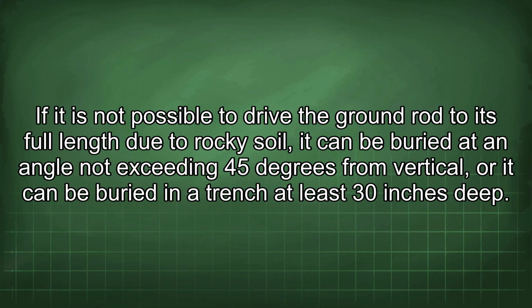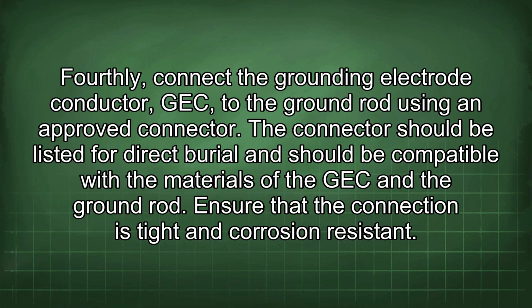If it is not possible to drive the ground rod to its full length due to rocky soil, it can be buried at an angle not exceeding 45 degrees from vertical, or it can be buried in a trench at least 30 inches deep. Fourthly, connect the grounding electrode conductor, GEC, to the ground rod using an approved connector. The connector should be listed for direct burial and should be compatible with the materials of the GEC and the ground rod. Ensure that the connection is tight and corrosion resistant.